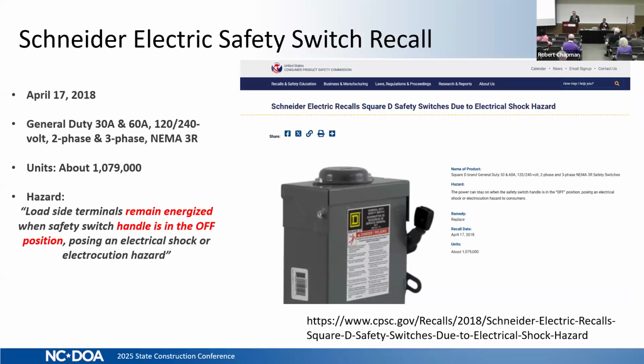So as I talk about these new guidances, I mentioned that one of the discoveries OSHA made is that injuries or fatalities were happening because the worker thought the equipment was de-energized. I turned off the switch. I locked it out and tagged it out. I thought it was dead. Well, the old adage of, yeah, I turned the switch off, we don't need to follow arc flash hazard analysis, we don't need to label our equipment, we don't need to buy PPE because our policy at this building and this facility and this campus is we always work de-energized, so we don't have to follow arc flash. This illustrates why OSHA is saying no more. You have to establish an electrical safety work condition, ESWC, in order to comply with these new guidance requirements. And this is one example why that is the case.